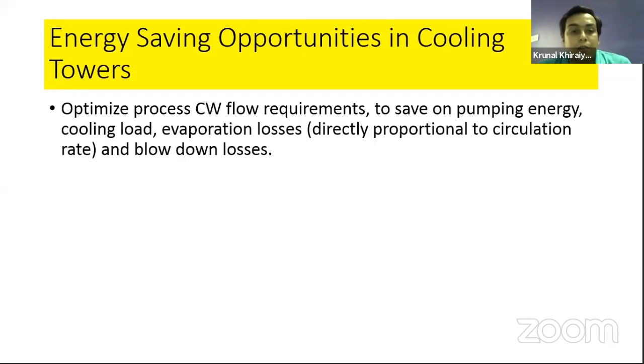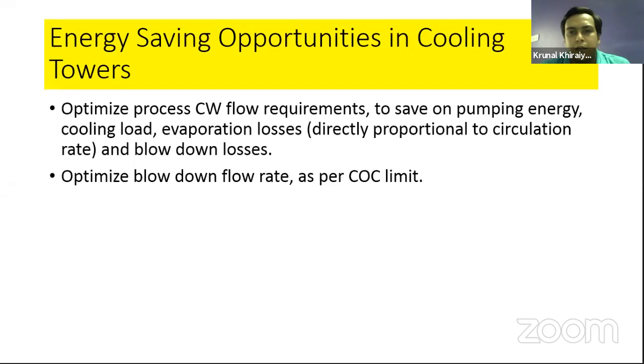The next, optimize process cooling water flow requirements as and when required. Suppose your vessel is 20 KL and you are doing some chemical processes, but you change the batch size so that instead of 20 KL you are using only 5 KL. At that time you need to optimize the flow rate, otherwise the pump requires more power. And as all of you know, the best efficiency point is also there, so you need to refer to the characteristic curves of the cooling water pump we are using. Then optimize the blowdown rate as per the COC. Yes, definitely it is required.